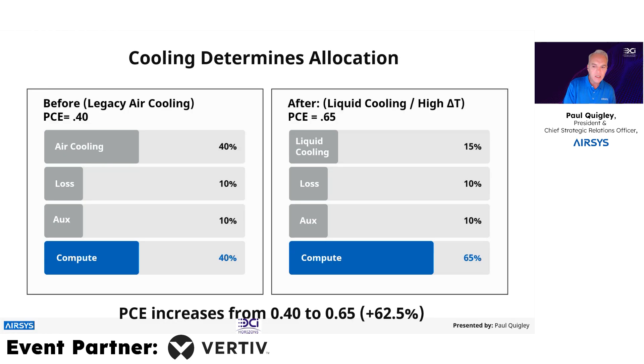And so we look at the heat rejection limits towards compute. It's really important. So let's look at the new drive to 45C from the Vera Rubin. AI increases the density, and that density increases the heat. So obviously it's apparent the heat rejection becomes the limiting factor now, not the server, not the racks, it's actually heat. The higher the temperature, the lower the overhead. That's such an important factor, I think even in the last session we didn't discuss this. This is where I think a critical pressure point exists in the industry, but there's not enough focus being made on that.